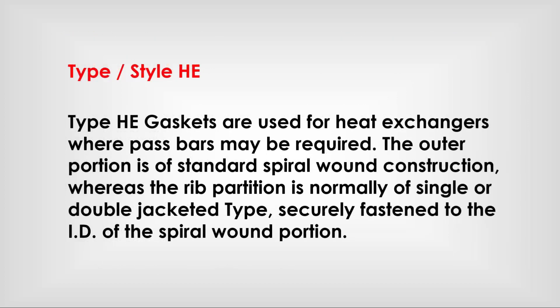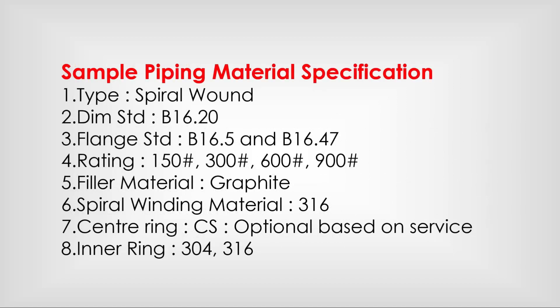Type style HE gaskets are used for heat exchangers where pass partitions may be required. The outer portion is of standard spiral construction, whereas the inner portion is normally of single or double jacket type, securely fastened to the ID of the spiral wound portion.